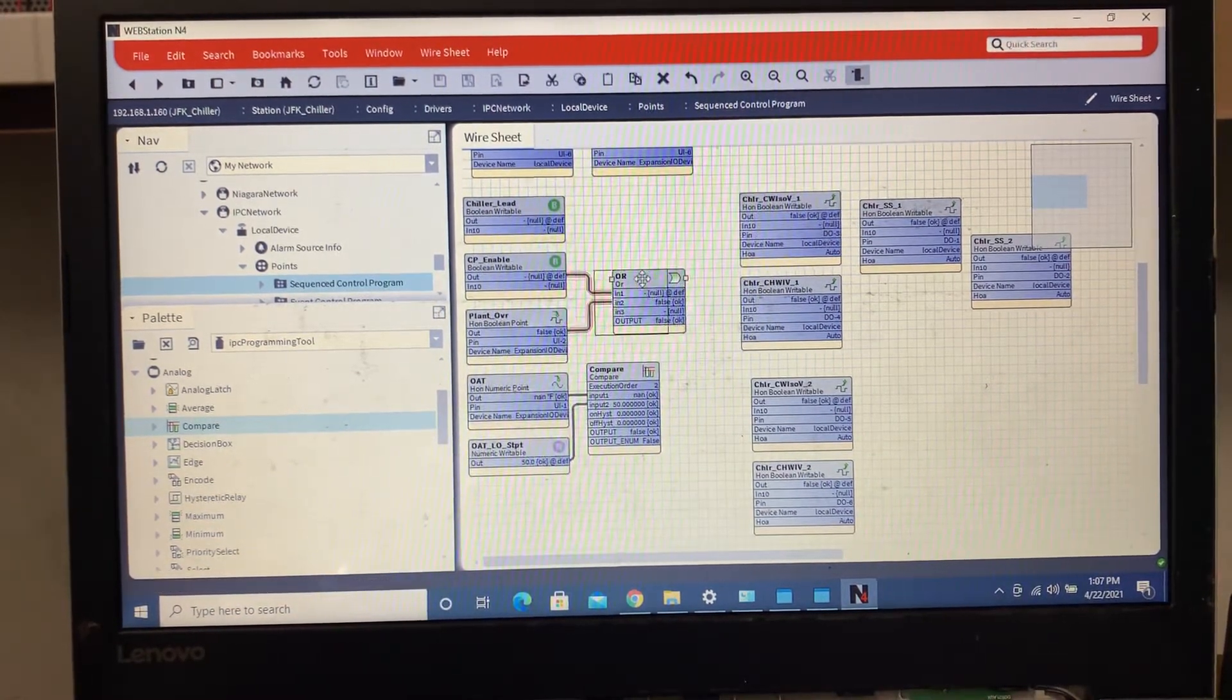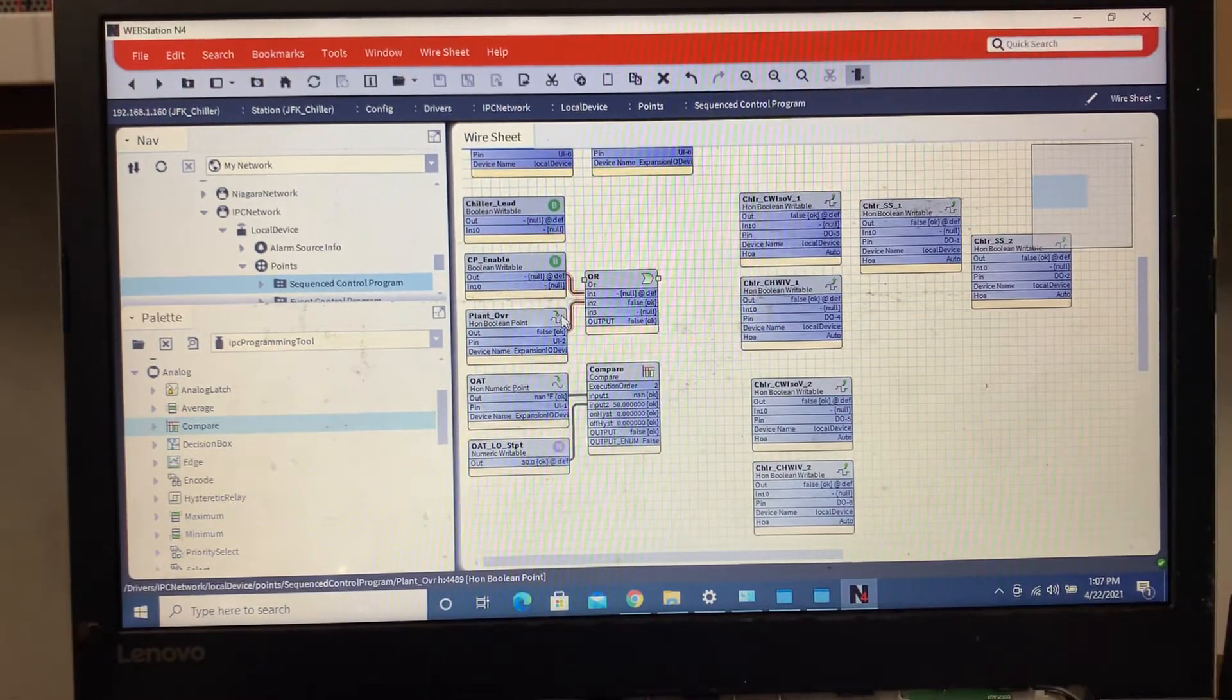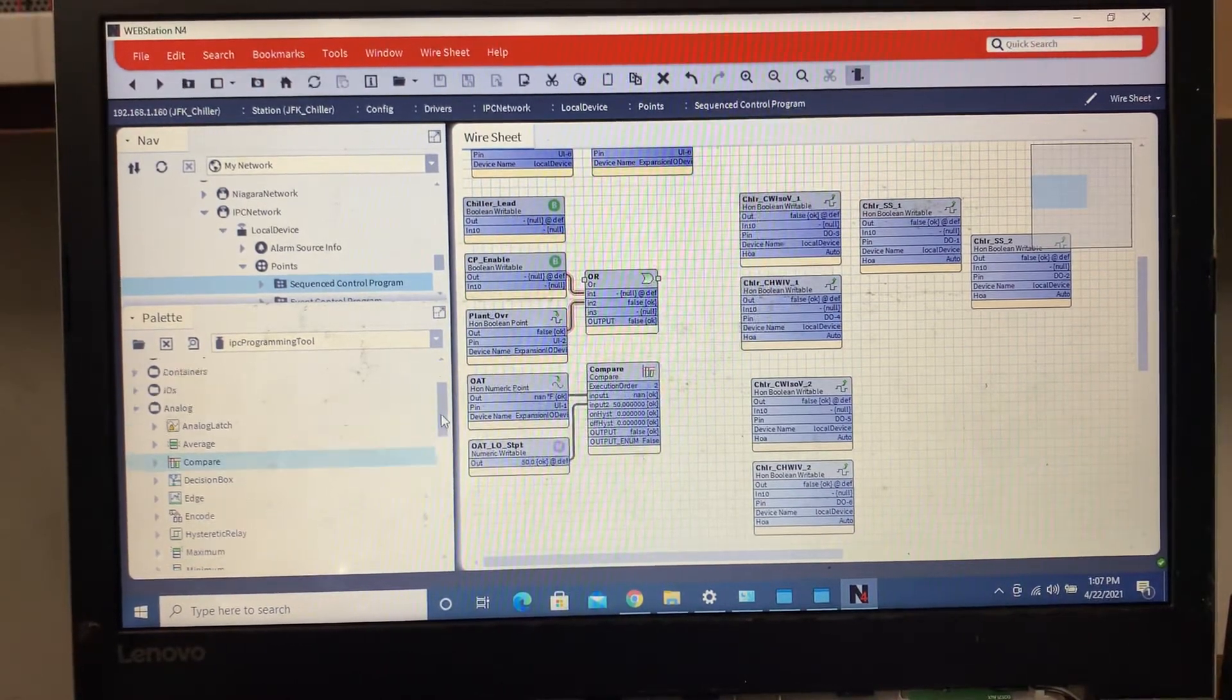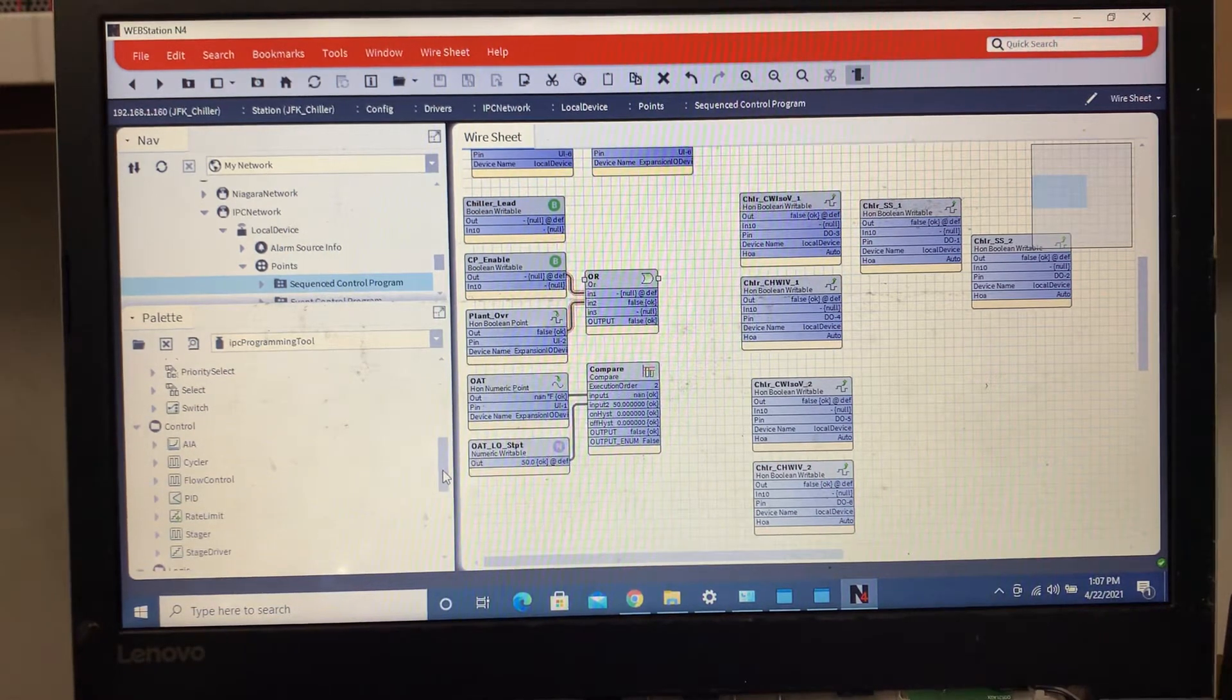Hold on, I gotta delete that, that's not the way I wanted it done. What I wanted to do is I want to take this OR block, basically saying if the central plant or the plant override is true, then what I want is an AND block. So go right here to logic, drag and drop an AND block.